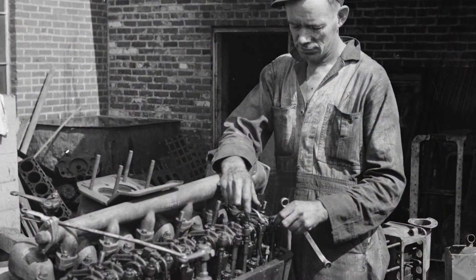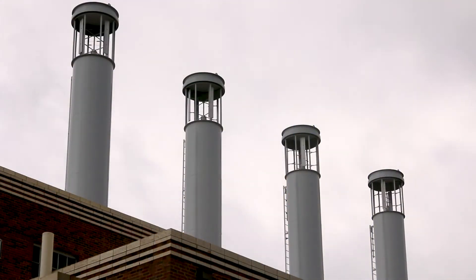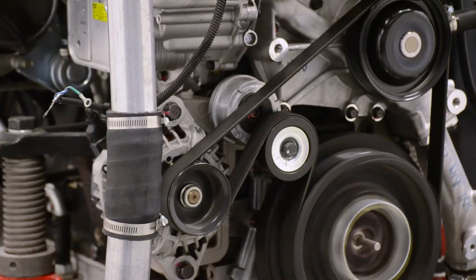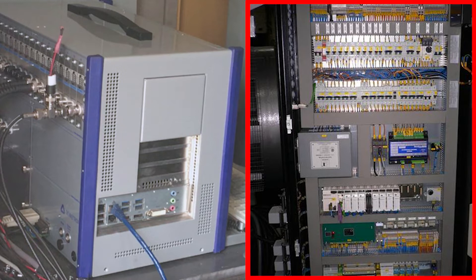These integral compressor engines were built back in the 40s and 50s. Back then, you're using kind of an averaging gauge and just getting the peak pressure coming out of the cylinder. As the technologies grew, it became more electronic, and in the 90s we started to see full-featured combustion monitoring systems. Most systems are two separate pieces of hardware — you've got your combustion monitoring system, and then you've got your engine control unit.